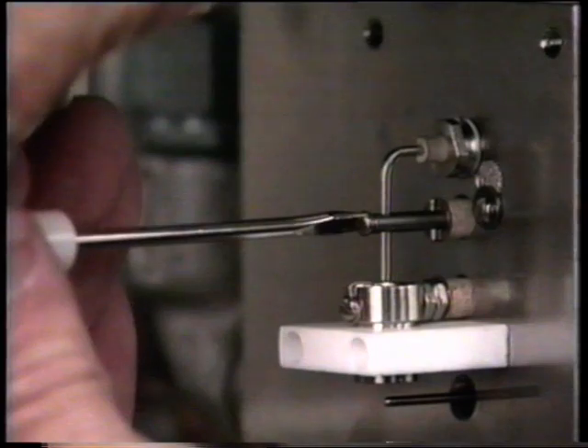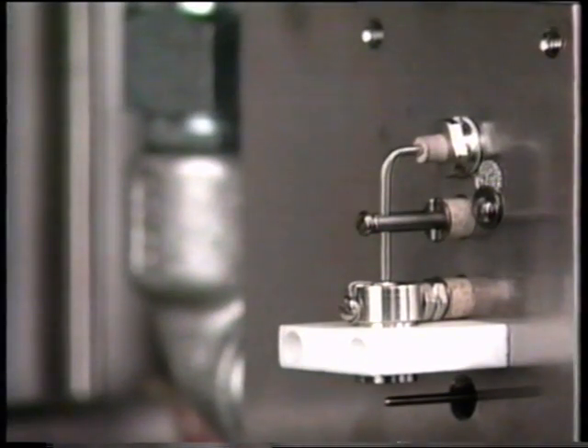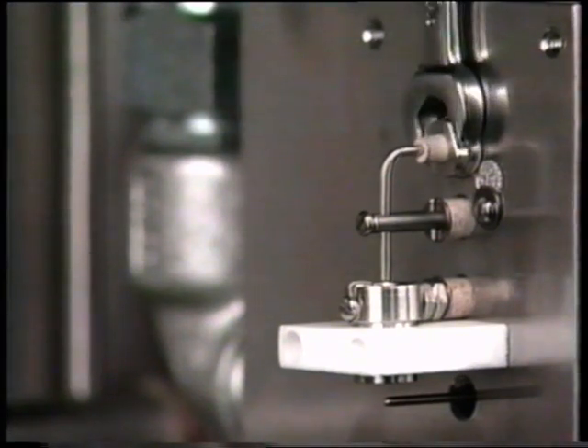Verify that the burner tip is still centered over the collector and tighten the screw of the bias ignite electrode. Tighten the burner clamp nut. Reinstall both the bias ignite and signal cables on their respective electrodes and ground clamps. Fasten them in place.